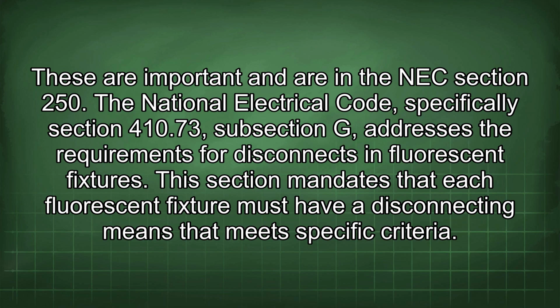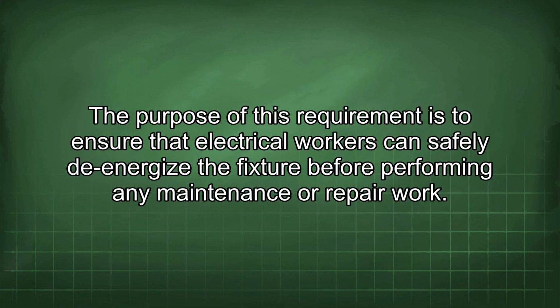The National Electrical Code, specifically Section 410.73, subsection G, addresses the requirements for disconnects in fluorescent fixtures. This section mandates that each fluorescent fixture must have a disconnecting means that meets specific criteria.